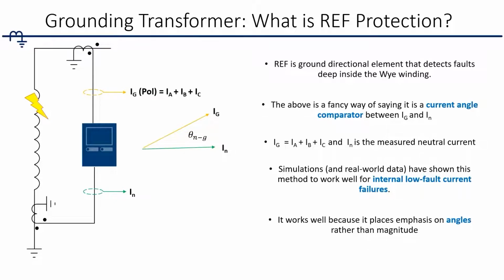REF is a ground directional element that detects faults deep inside the winding, and that's kind of a fancy way of saying it's a current angle comparator. What it does is there are two sets of CTs on a transformer. There's a set on the top of the bushing and at the neutral, and the top CTs are summed together, where you sum up your phase currents and you can get the effective ground current contribution into the transformer, and then you have your neutral measurement. And what it's doing is comparing the angular difference between the two. This is kind of a simplified way of looking at that.